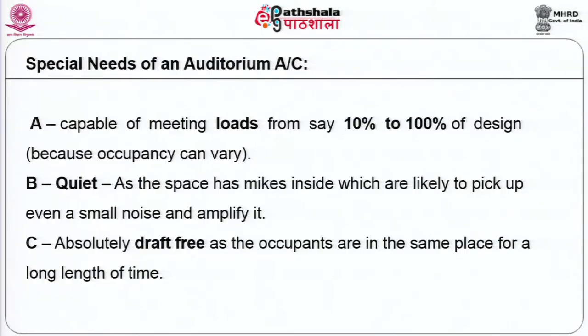The next important criterion would be that the equipment has to be quiet. Because in an auditorium, it is invariably audio communication which has to occur, and there are powerful mics in the place. So, any noise which comes into the area is likely to get amplified by the mic and make the speaker virtually unheard. The other important aspect is to have draft free air conditioning, because people will be sitting in their place in a continued area for a continued occupancy for a little longer than normal. So, if there is a draft and he feels cold, he will just not be able to change his place. So, out of a requirement for comfort, it is necessary to have air conditioning which is draft free.